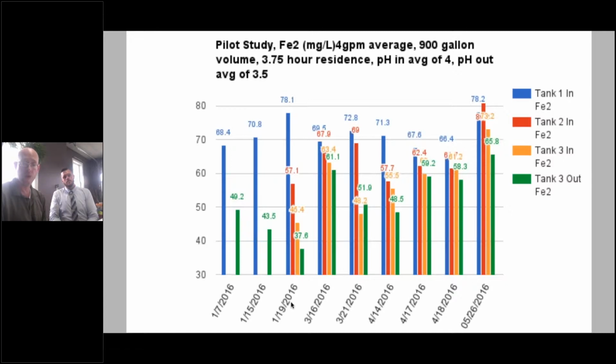But one thing I do want to point out is we go from 119 to 316. We got a 2-month jump there, almost a full 2 months. So this system has been operating for 4 months without me touching it. I didn't stir it, I didn't flush it, I didn't drain it, I didn't do anything. And by the time you get down to 316, treatment rates are really falling off. Well, what's going on? And then 321, hey, look at that. The back end actually jumps back up again.